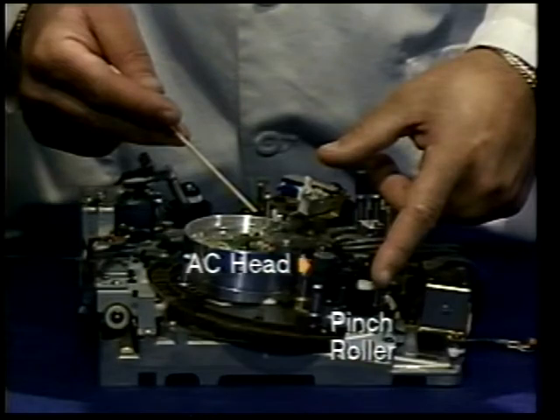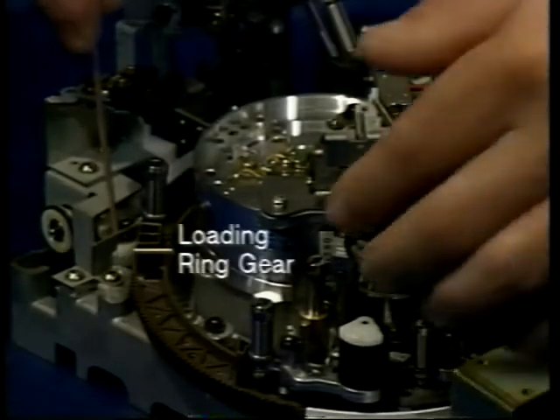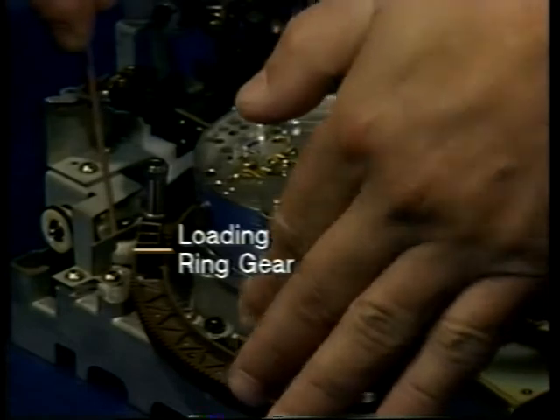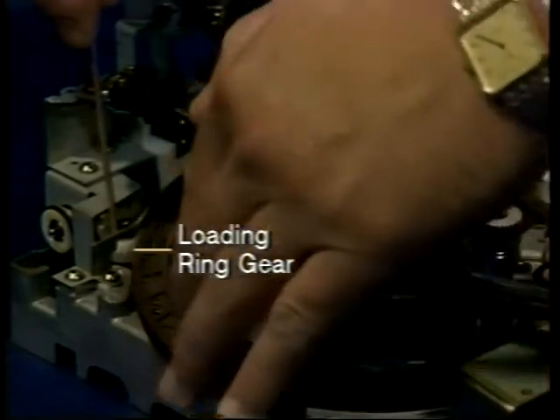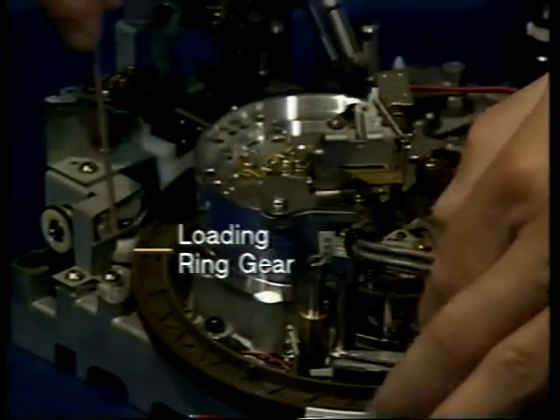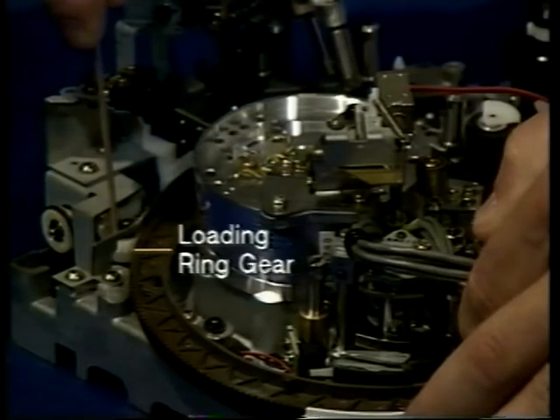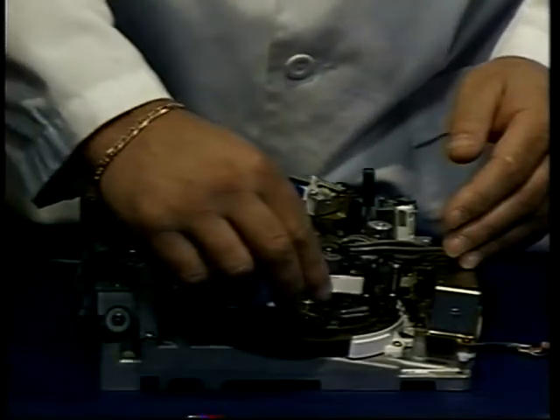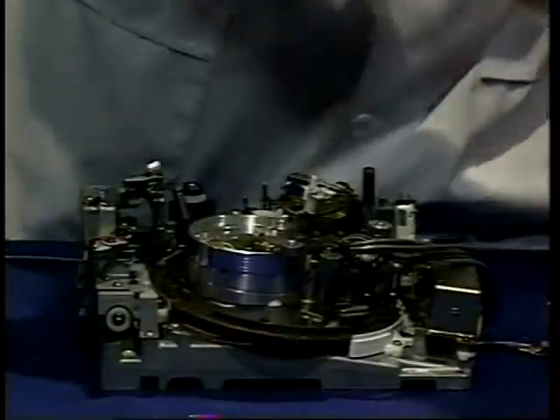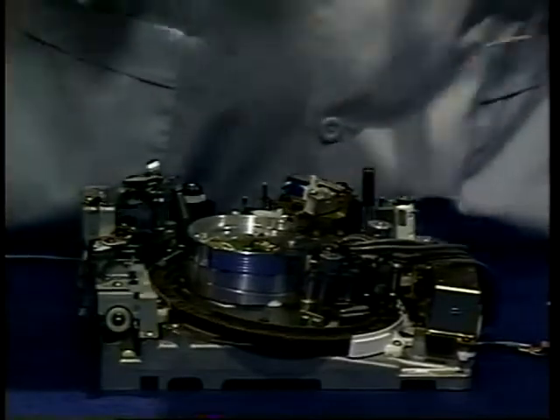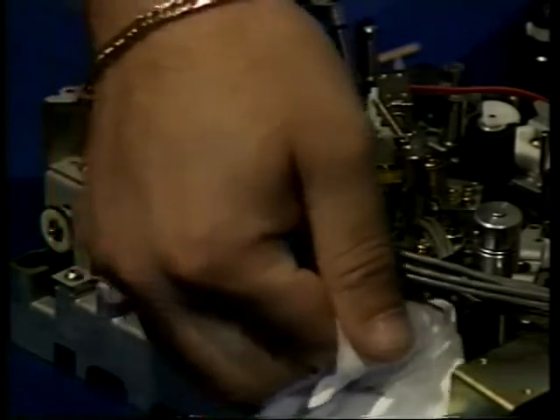To move the loading ring, push down on the loading ring gear, which allows you to move the pinch roller and guides away from the AC head. You now have access to the AC head for cleaning. The AC heads can be cleaned with a chamois cloth stick, or with the lint-free Texwipe as shown here. The critical area to concentrate on is again under that plate where channel 2 is located.